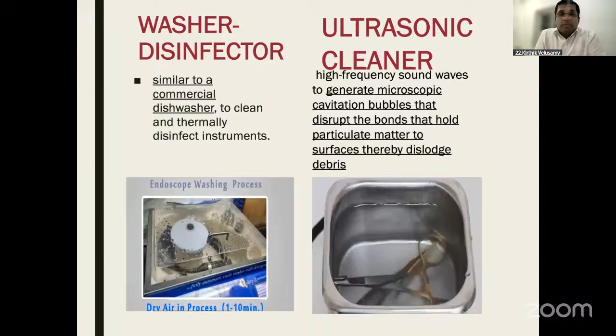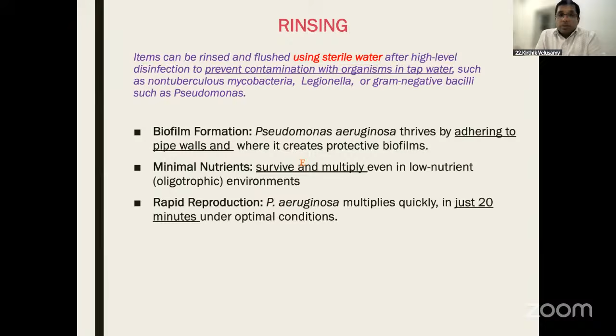Once the manual scrubbing followed by soaking is done, then the most important part is rinsing. We use RO water because tap water is heavily contaminated with so many organisms. As a urologist, we are more worried about pseudomonas because they adhere to the pipe walls. They survive and multiply within just 20 minutes and form a biofilm. So to avoid that, we always need to use RO sterilized water. This is how we do rinsing.